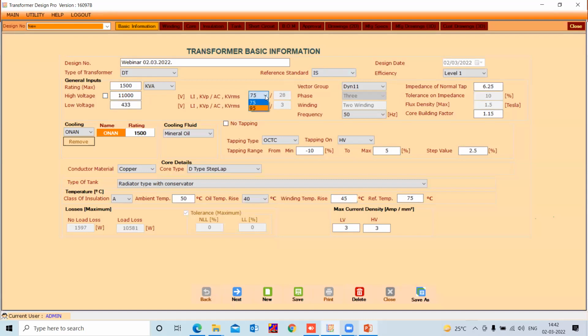Then you can choose the reference standards. Let us go to the top first. Various reference standards can be chosen, whether it is Indian Standard, IEC, ANSI, CBIP, ECBC, SANS, that's generally followed in South Africa, then European Ecodesign, or GOST, that's mainly in Russia and nearby, or WAPDA, which is prevalent in Pakistan. So let's choose any of the reference standards and go for the efficiency.